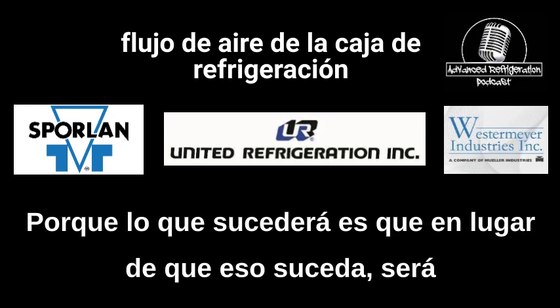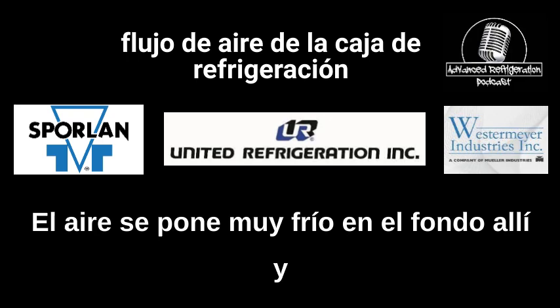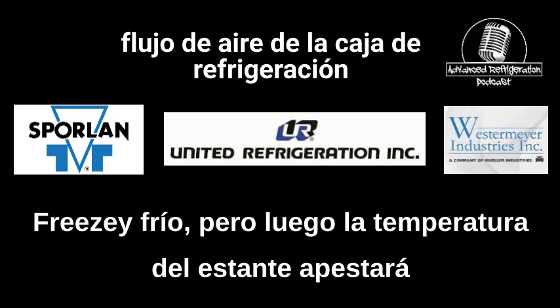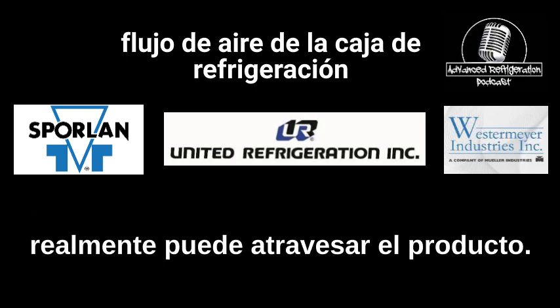Because what'll happen is it'll just come out the back wall and go directly down to the bottom deck that doesn't need the shelf extender. The air gets really cold at the bottom there, and usually the product at the bottom will be freezing cold, but then the shelf temperature will suck. That's when those cases need that shelf extender to bridge that gap so the air can actually go across the product.